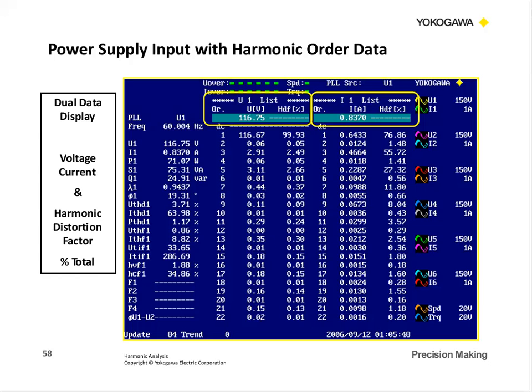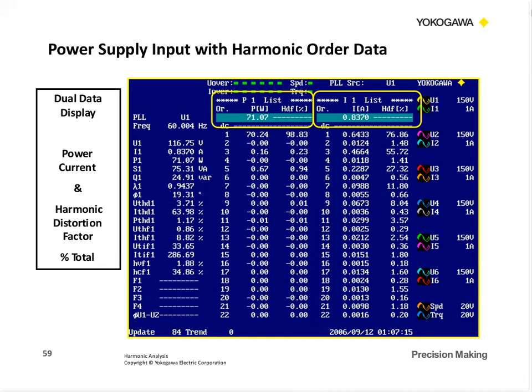Okay, so percent of fundamental is the harmonic distortion factor. So we can go through and look at the 22 orders of that, and here's the current over here. So we looked at the voltage and the current, and just a list of data for you. Then we can break this down a little bit more. Here I put in the power measurement, and you can see how this kind of goes away. So, some of them are negative. That's because we lost our voltage and current reference, they are not always there. Even though we got current that goes out pretty high, we lose the power because the voltage harmonics were not there.